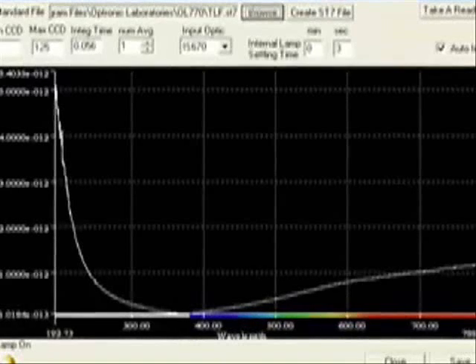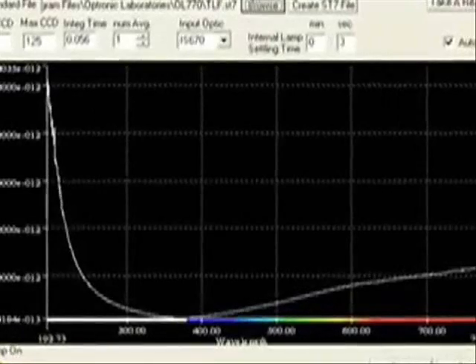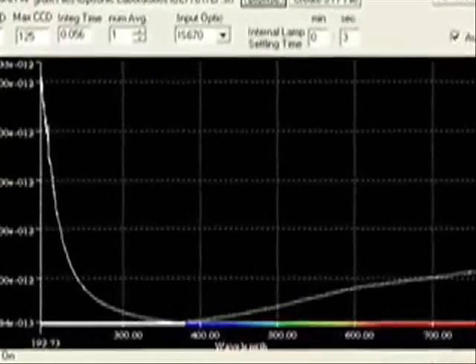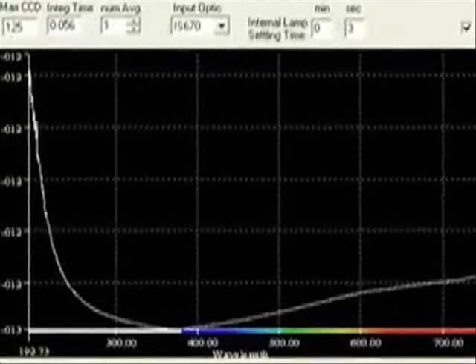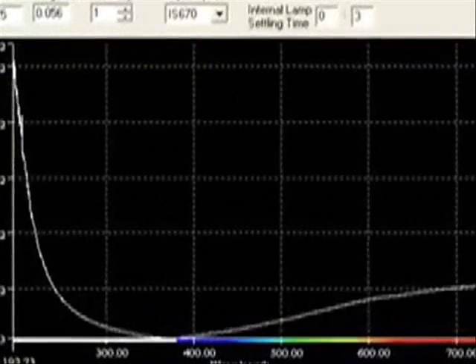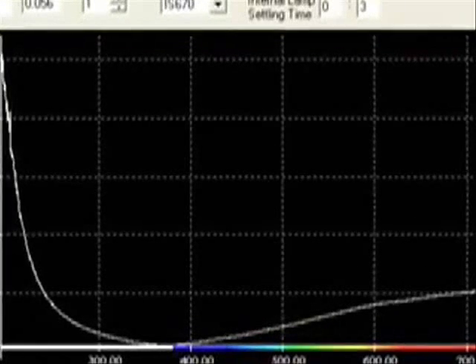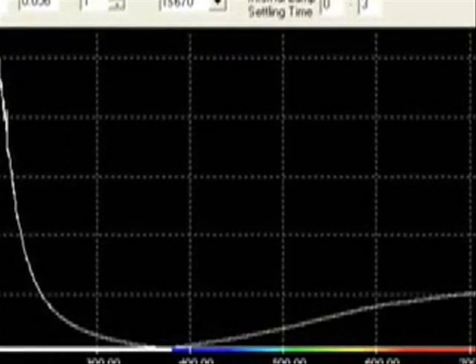With all metrology instruments, NIST traceable calibration is critical. Typically, maintaining traceability usually involves long periods of having a unit out of house and can become expensive. The OL-770 LED can be recalibrated on site, and it's as easy as taking a measurement.